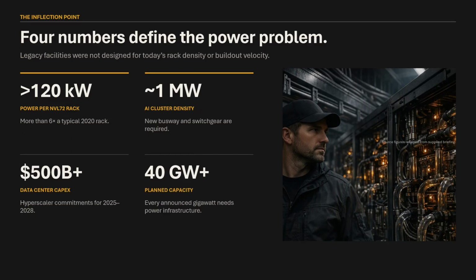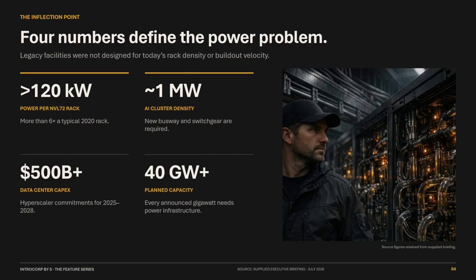These 4 figures show why legacy assumptions no longer hold. A single NVL72 rack can draw more than 120 kilowatts, over 6 times a typical 2020 rack. At cluster scale, demand approaches 1 megawatt, forcing changes to busway and switchgear. At the same time, the briefing tracks more than $500 billion of data center capital commitments and over 40 gigawatts of planned capacity.